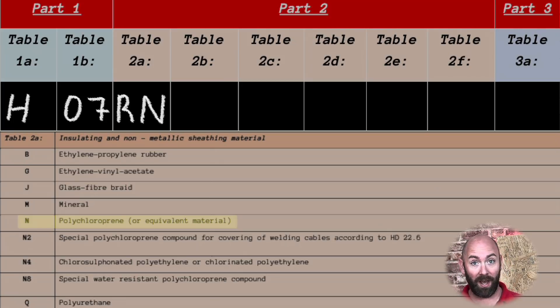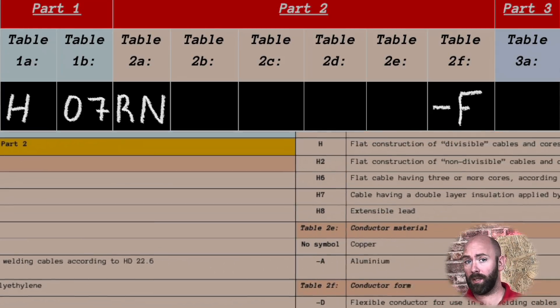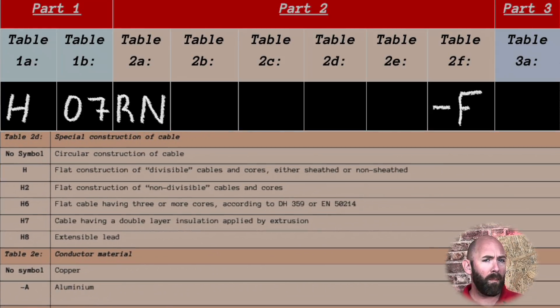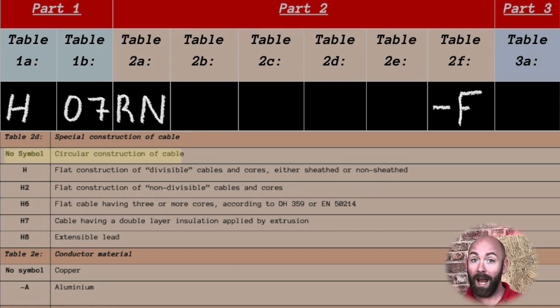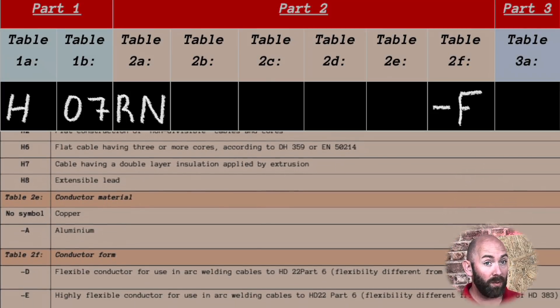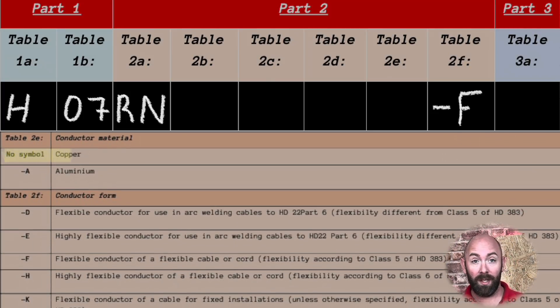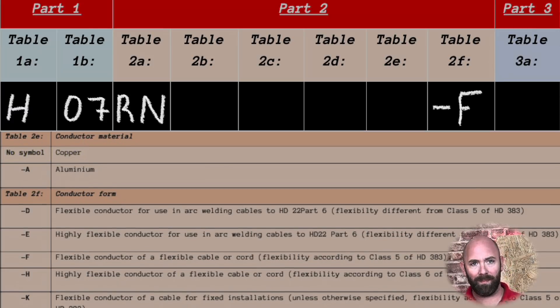If you're wondering why we're leaving blanks in the code, they do mean something. A blank in position 2D means the cable is circular, and the list shows the different special construction cable types. A blank in 2E tells us that the cable is a copper cable — dash A would be aluminium.